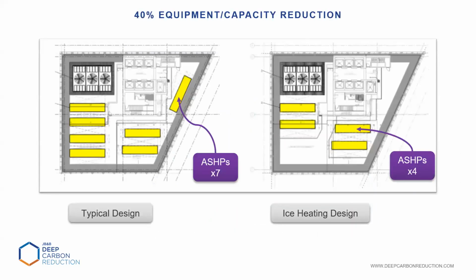What that looks like on an actual roof: a typical design would have 7 air source heat pumps taking up all your roof space, along with cooling towers and the core area. But when you deploy ice heating, you only need 4 air source heat pumps, and all the other equipment can live indoors, anywhere in the basement or existing mechanical room — you don't need outdoor air access like the heat pumps require.